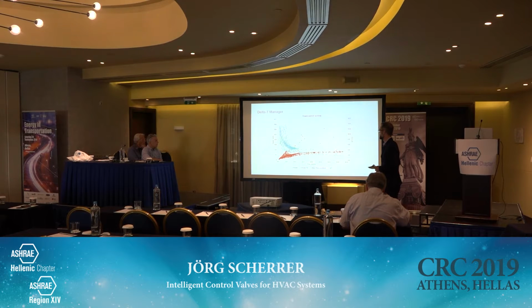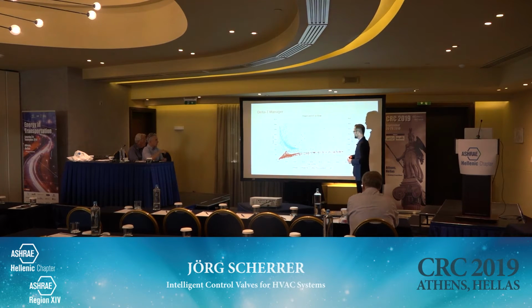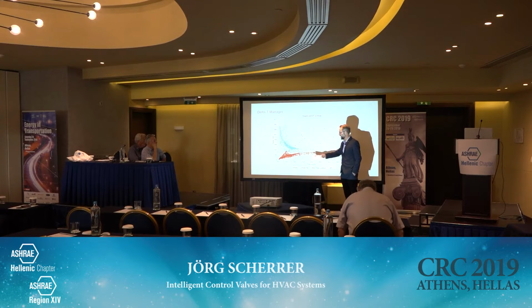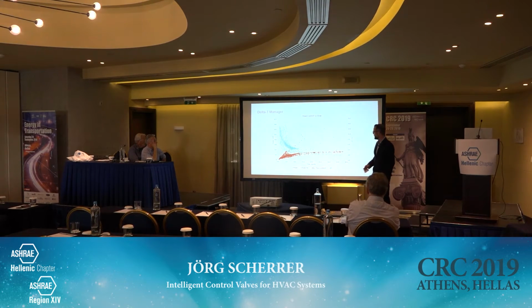Here is a picture of how it looks in real life. So these are operating points from a real installation. We see here the red points is the power output on the heat exchanger, and with this cooling application, the blue points is my differential temperature, delta T. Now I see very clearly here my pump runs at 100% with a flow rate of 38 cubic meters per hour and with a power output of about 80 kilowatt.